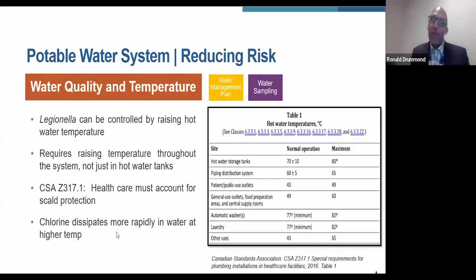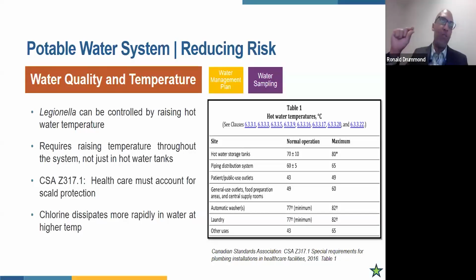So in terms of water quality and temperature, CSA Z317.1 does spell out the requirements for hot water in healthcare service providers. So table 1 shows all that information that's there. Not only the temperature that you have to be at, but like by user, what your hot water temperature is allowed to be. So one thing to note is that delta between those users. Those lower values are in patient care areas, and it's important to understand that it has to be lower in those areas because we're trying to prevent scald in those patient populations. So your infrastructure may not be sophisticated enough to ensure that patients or equipment are protected from raising the hot water temperature. So make sure to do your investigation beforehand before you unilaterally go ahead and raise the temperature throughout the system.